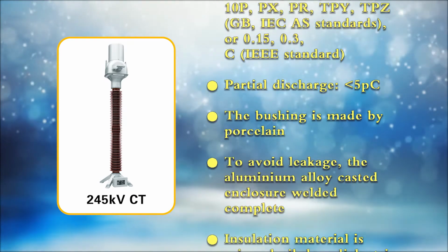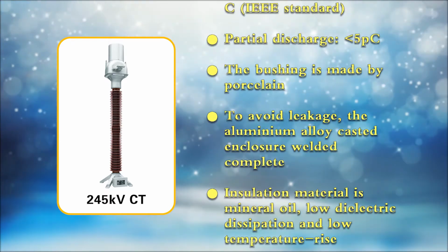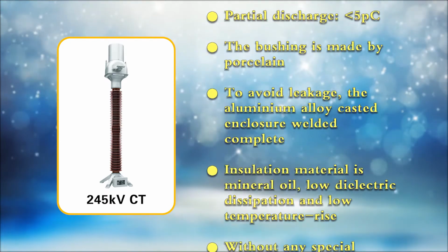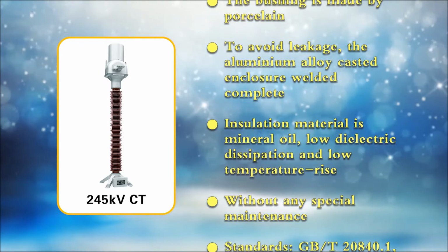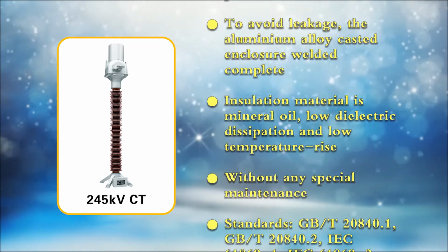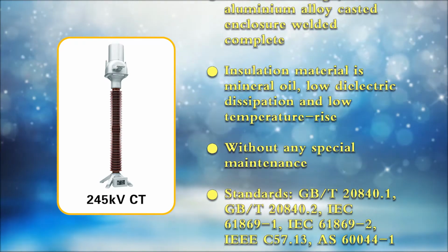The bushing is made of porcelain. To avoid leakage, the aluminium alloy cast enclosure is welded complete. Insulation material is mineral oil, with low dielectric dissipation and low temperature rise, without any special maintenance. Standards.